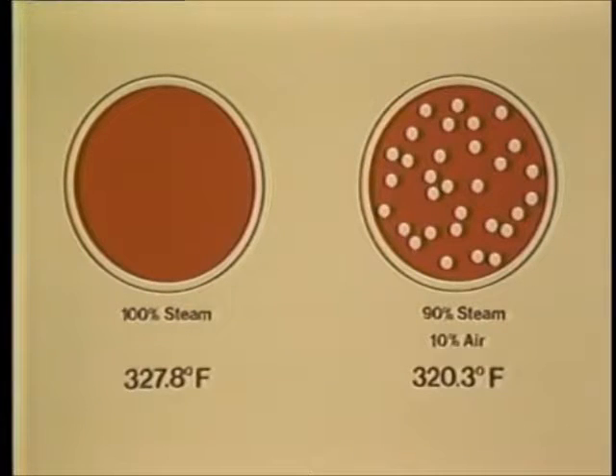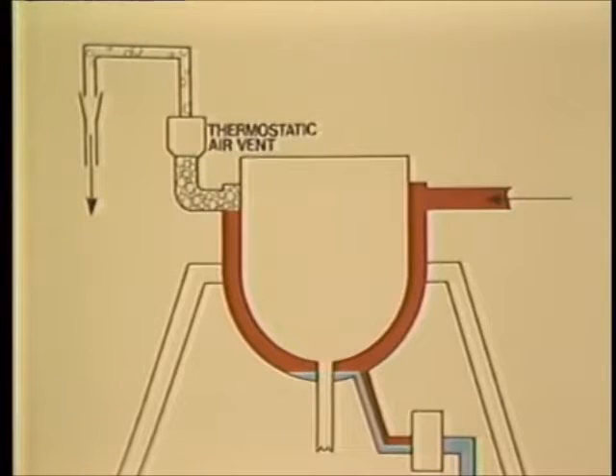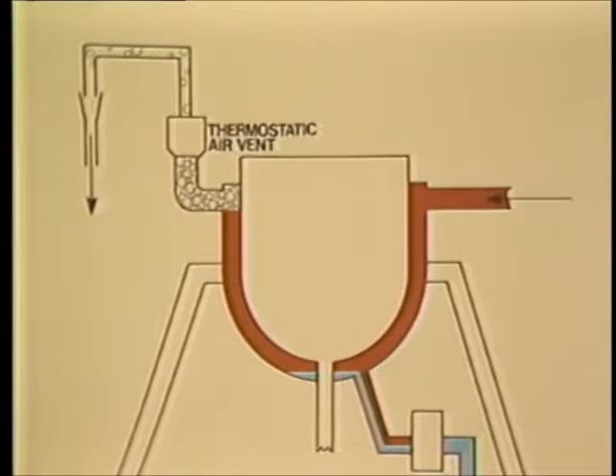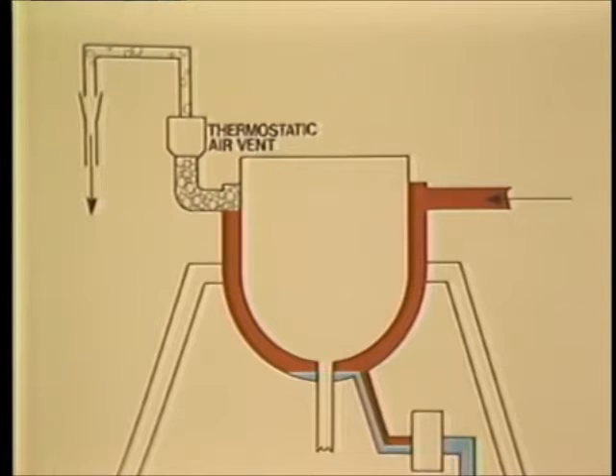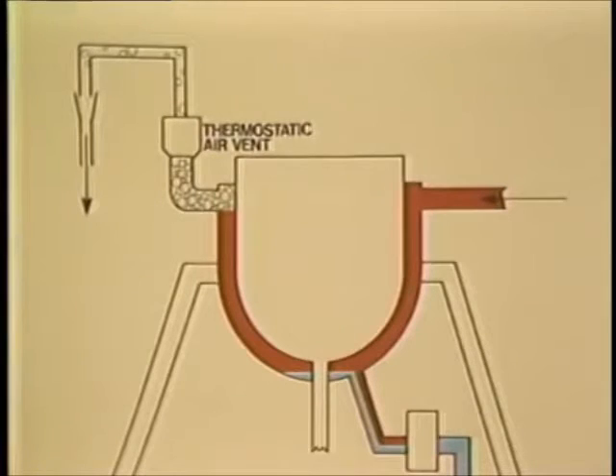In addition, an air-steam mixture has a lower temperature than pure steam. Install thermostatic air vents at the top of the heat exchanger's steam space and as far from the steam inlet as possible. Air vents are typically used on jacketed kettles, retorts, vulcanizers, jacketed sterilizers, and most batch process equipment.